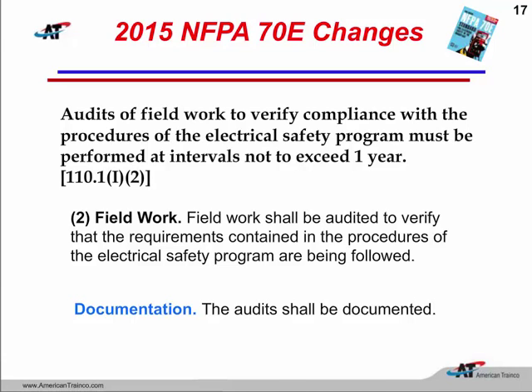And this doesn't mean that we have to audit every single worker out there, but we do have to go out and audit field work. We can go out on the manufacturing floor or go to the site that our worker is at that particular day if they are an outside contractor. And we're going to have to make sure that they are following NFPA 70E, and we're going to have to document that and put that in our files. OSHA is going to want to see that in the event that they do arrive and want to take a look at all of your documentation.